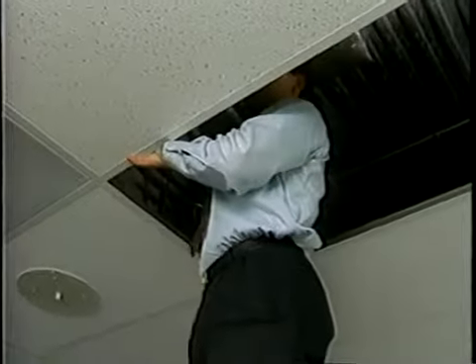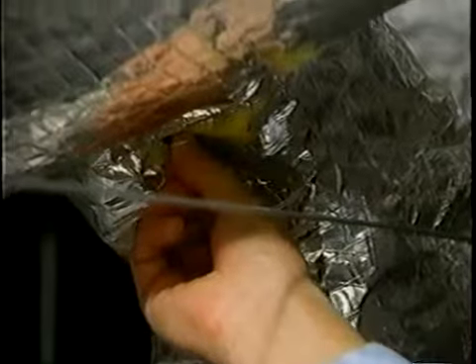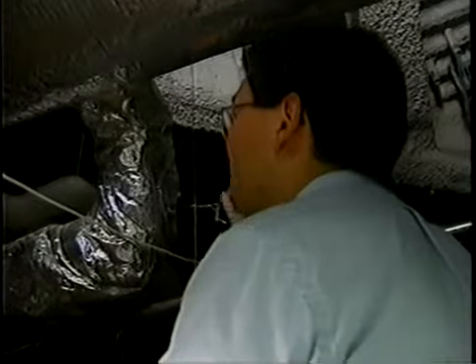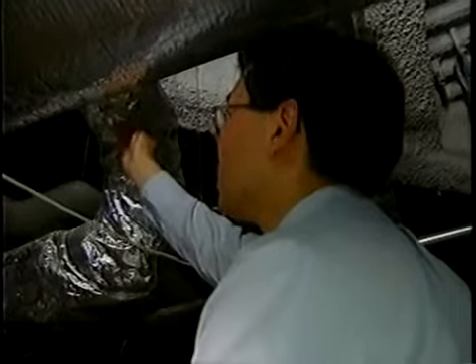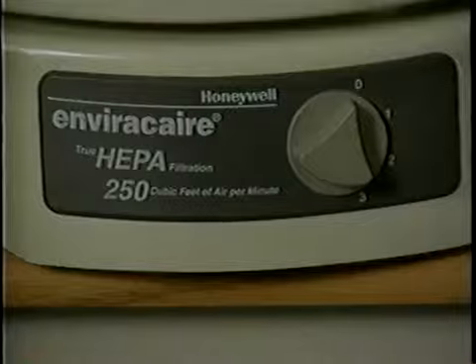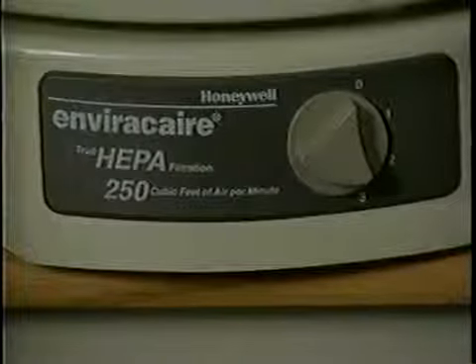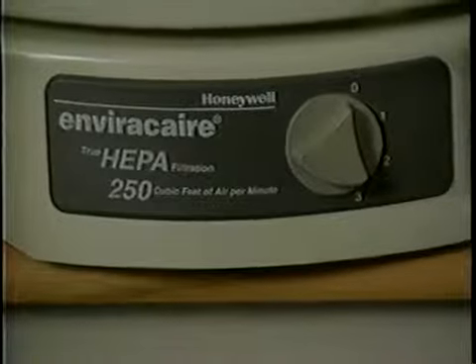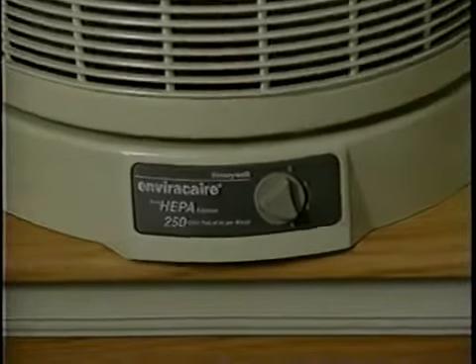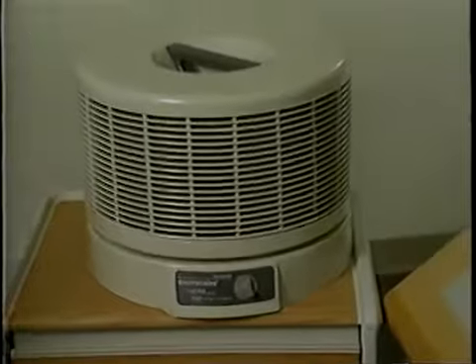So, where can you get this extra air from? Well, you have two basic options. You can either increase airflow by adjusting, also called rebalancing, the mechanical system to exhaust more air. This means adjusting the ventilation system that serves the isolation room and should only be done by facility engineers or by a certified air balance contractor. Or you can use a HEPA filter unit to make up the required CFM difference. Next, we'll talk about what happens to the air after it leaves the isolation room.